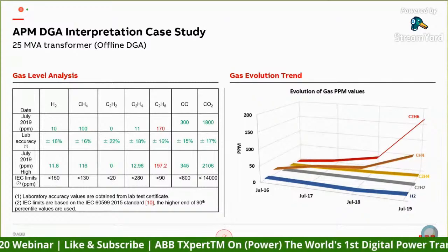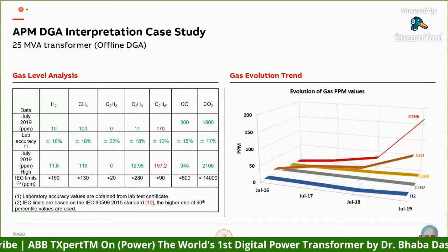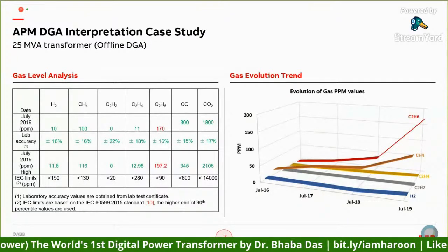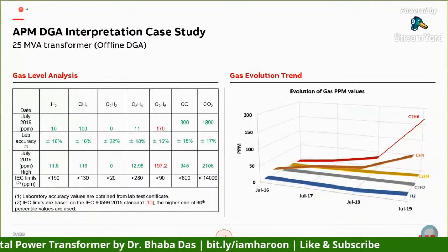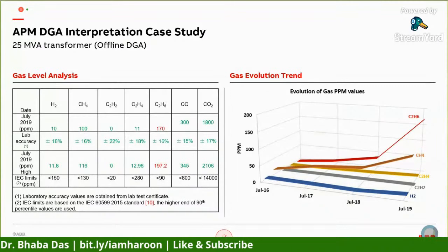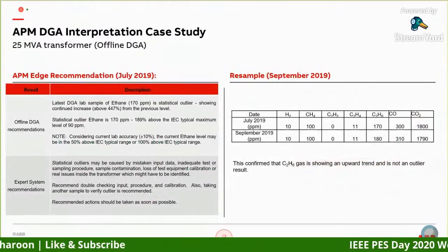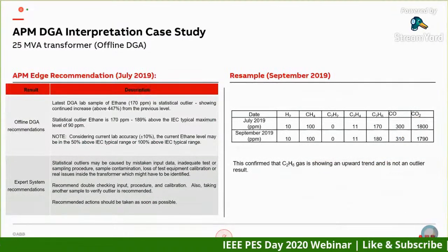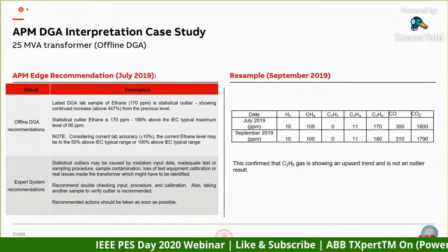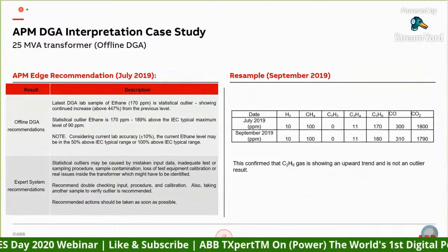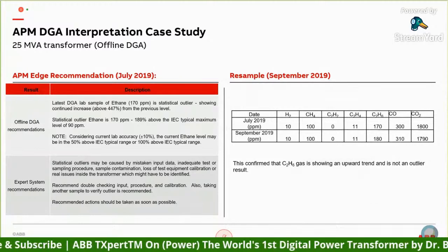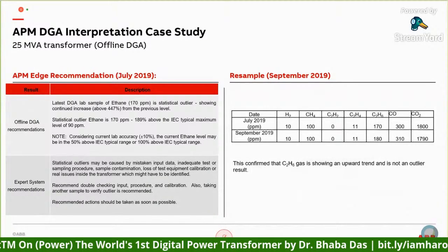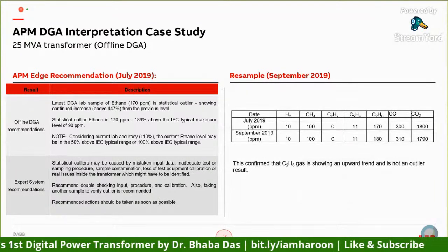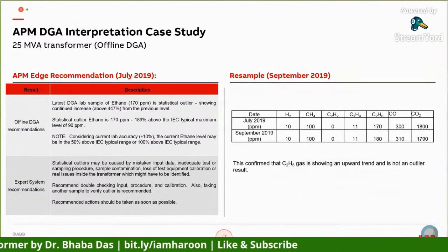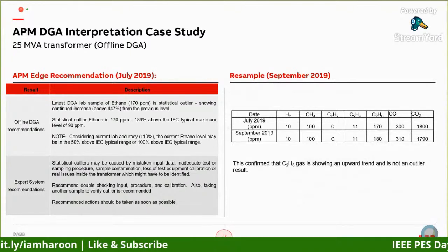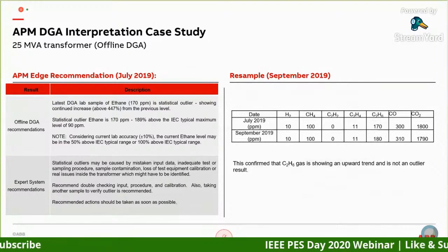And you can see the ethane gas levels have gone up considerably. Once we put in this data, the software automatically said that this ethane gas is a statistical outlier because we are seeing almost a 447% increase from the previous level. And the expert system straight away recommended that it may be a mistake in the input data, it may be something to do with sample contamination, and it recommended please double check.